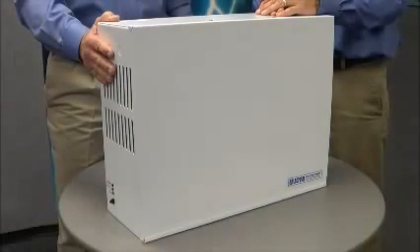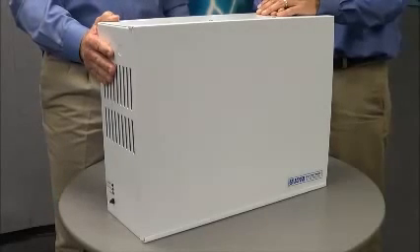There are many applications where the IOTA IIS inverter product line provides a better solution to address your emergency lighting requirements. One of those is the new LED lighting technology. With the IOTA IIS inverter, we provide line voltage to the LED driver, which eliminates any compatibility issues between the emergency lighting system and the LED driver. Another great application for the IOTA inverter is to address your outdoor emergency lighting requirements. The inverter can be mounted indoors in a climate-controlled environment and operate exterior fixtures such as step lights, bollards, or handrails up to 1,000 feet away.